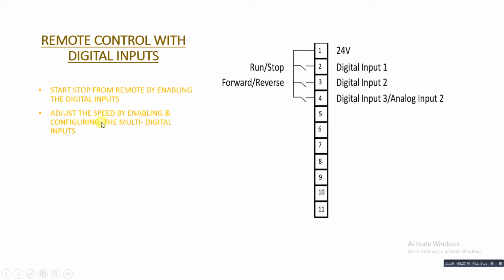The same way you can adjust the speed by configuring multiple digital inputs. There are several digital inputs available. Each digital input has some specific configuration. By setting this digital input configuration, you can even change the VFD speed. So this is the way how you can remotely control this VFD by digital inputs.